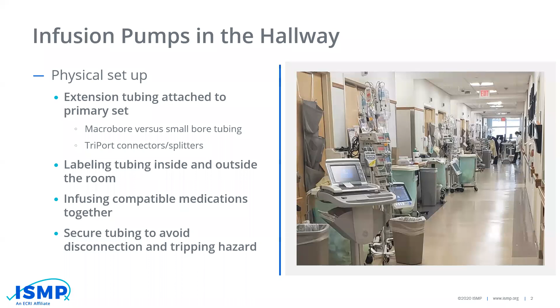The whole reason for doing this, by the way, you may have guessed, was to reduce nursing staff exposure. They didn't have to go into the room. With the pumps outside, the bag changes could be done outside. If there were pump alarms, that could be done without having to gown with PPE, personal protective equipment. So you could even conserve on the use of personal protective equipment.